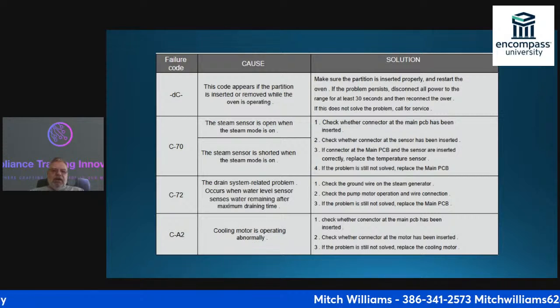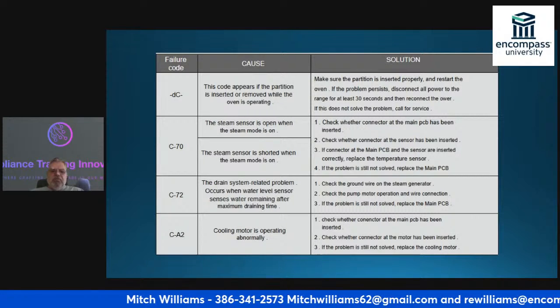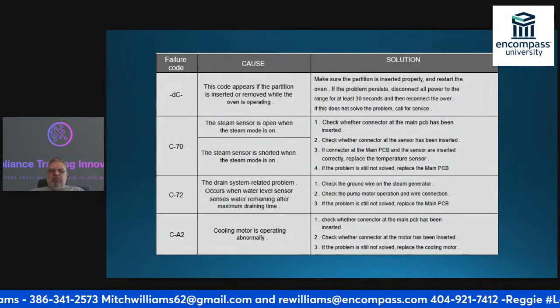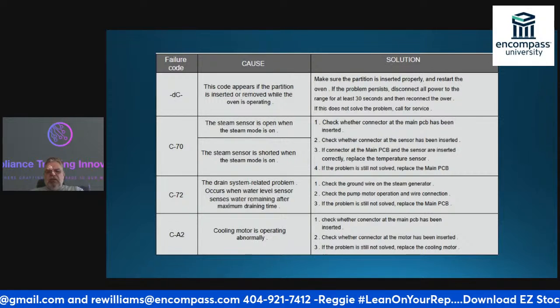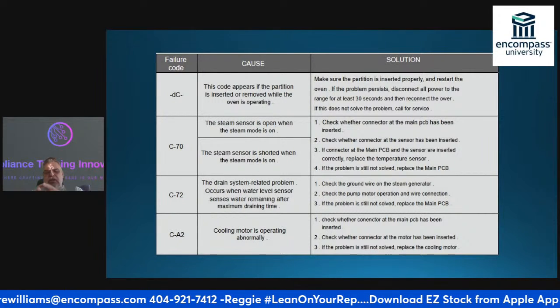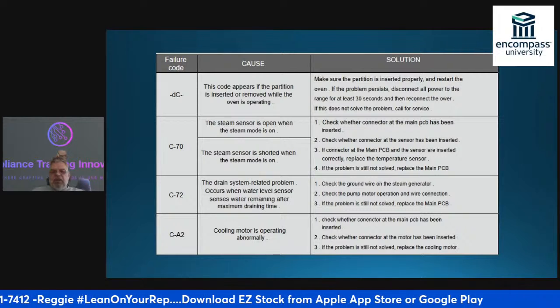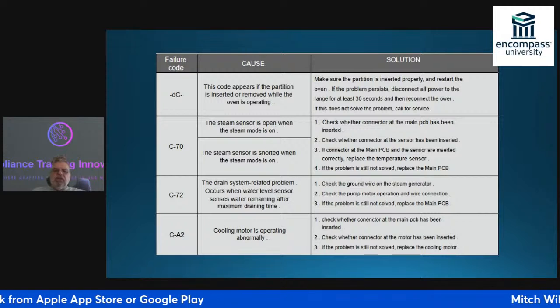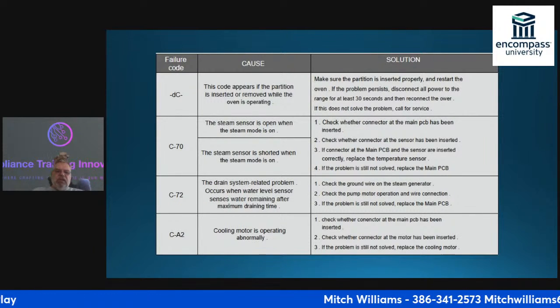Okay. If I get a C70, the steam sensor is open when the steam mode is on. That's going to check whether the connector on the main PCB has been inserted. Check the connector at the main sensor, make sure that it is in properly. If the connector of the main PCB and the sensor are inserted correctly, replace the temperature sensor. If the problem still persists, replace the main PCB. That's for a C70 error.